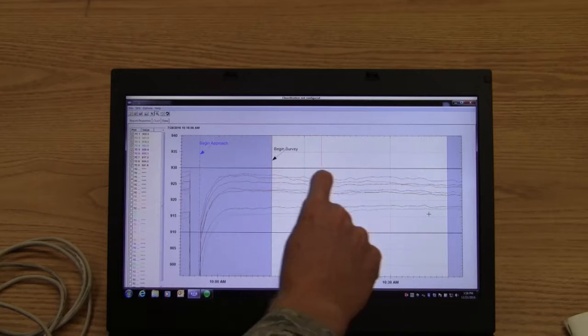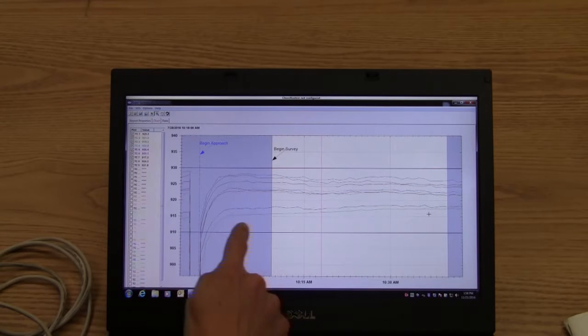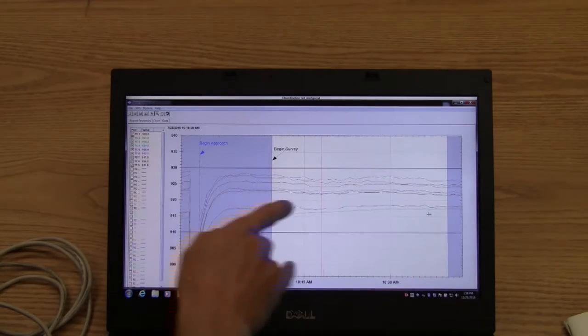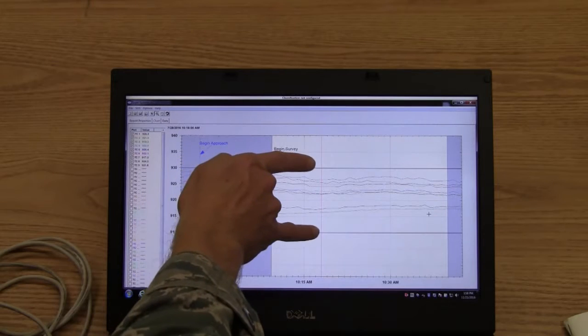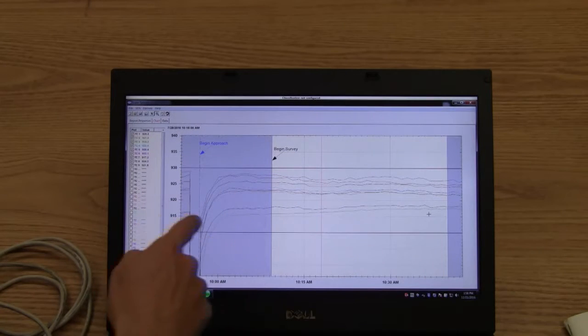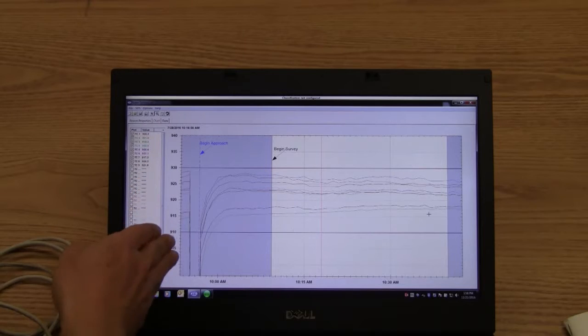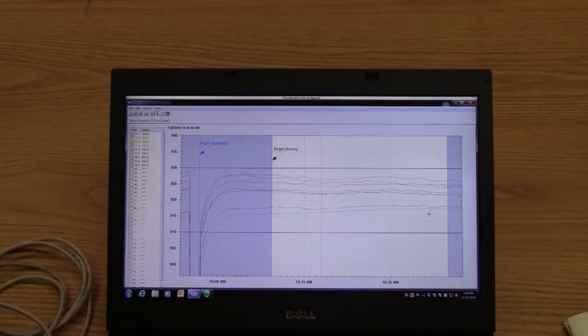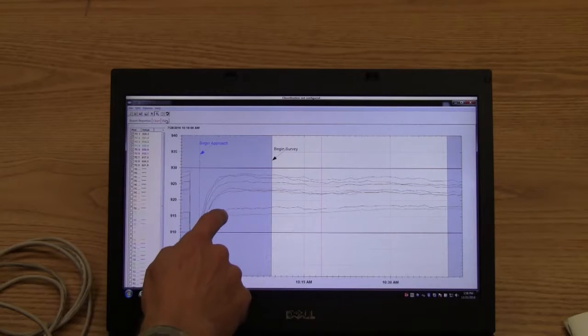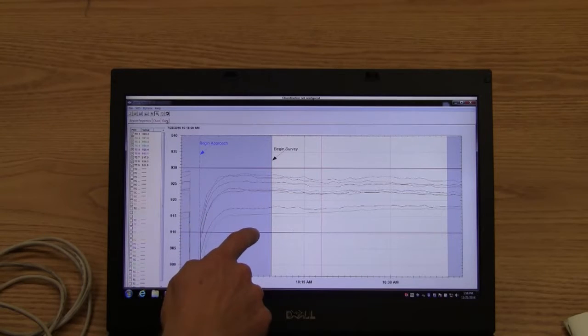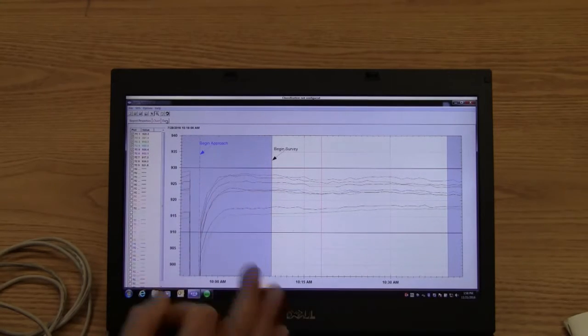All of my thermocouple lines, all of my reported data for my thermocouples is well within my upper and lower tolerance lines, right? So at this survey, I was running it at 920 plus or minus 10 degrees. So my range is 910 to 930. But I'm a creature of habit, and so I'm going to look at my data anyway. If I had a line that was really close to the lower or upper limit, you definitely want to go to your data tab.